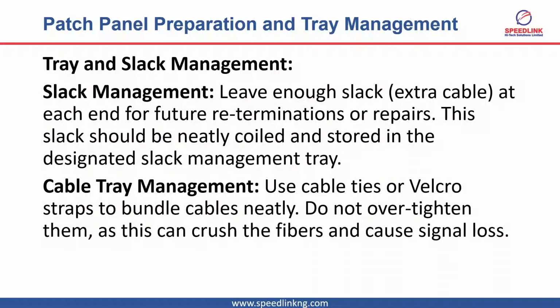Let's say, for instance, you are terminating a cable at a pole. You want to put an enclosure at that pole. Now, you don't just measure directly from the pole to the ground and cut, isn't it? You have to add some form of excess, which you call slack, which you use for termination purposes. Now, you're not just looking at the one you use for the termination of today's work. So looking at, okay, what if something happened and I have to re-terminate this cable all over again? It's still the slack that you have kept that you're going to use to do that work, isn't it? So you have to keep enough slack.